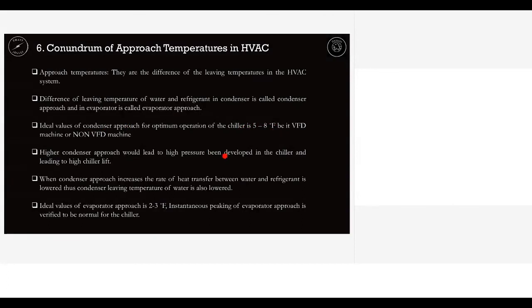Similarly, there is an evaporator approach, but since the evaporator circuit is mostly a closed loop in water-cooled chillers, it's not as big a factor, though there is still a range, normally 2 to 3 degrees Fahrenheit.